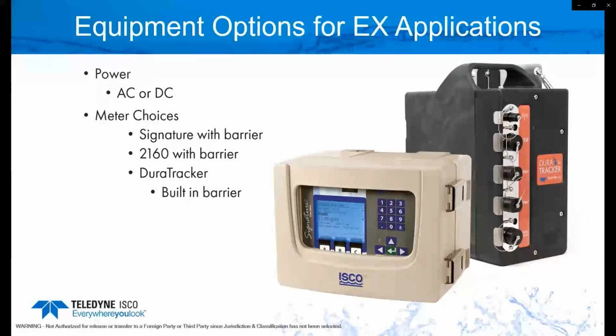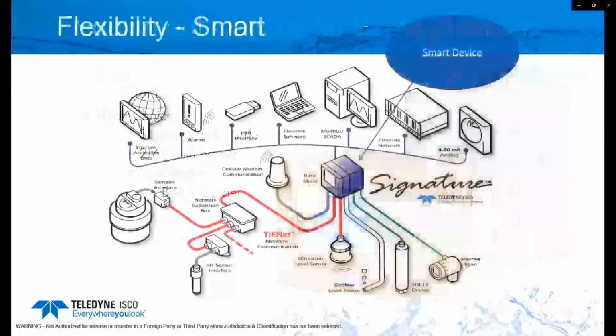So in our case, the signature with the barrier would be out of the hazard area. Same thing with the 2160. But the DuraTracker EX, the black box unit you see there, has a built-in barrier right inside it, so that can now be located in the manhole environment or the hazardous location. So with any equipment you look at, you want to make sure you understand what that equipment is rated and how it's going to be able to be set up in your environment.